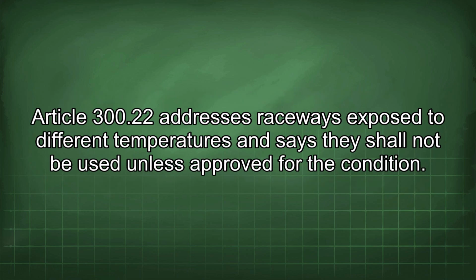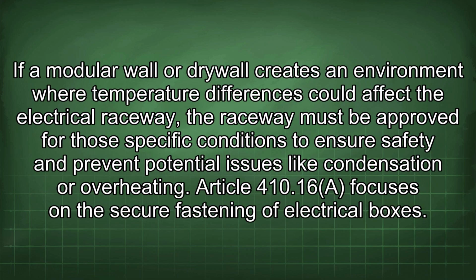Article 300.22 addresses raceways exposed to different temperatures and says they shall not be used unless approved for the condition. If a modular wall or drywall creates an environment where temperature differences could affect the electrical raceway, the raceway must be approved for those specific conditions to ensure safety and prevent potential issues like condensation or overheating.